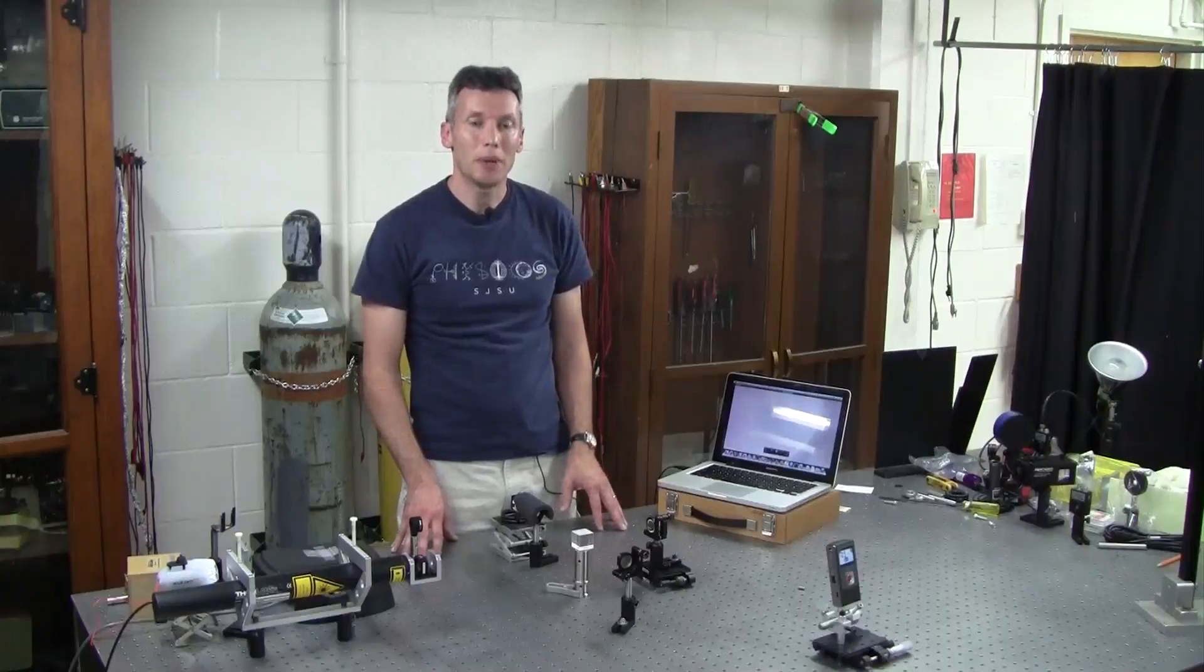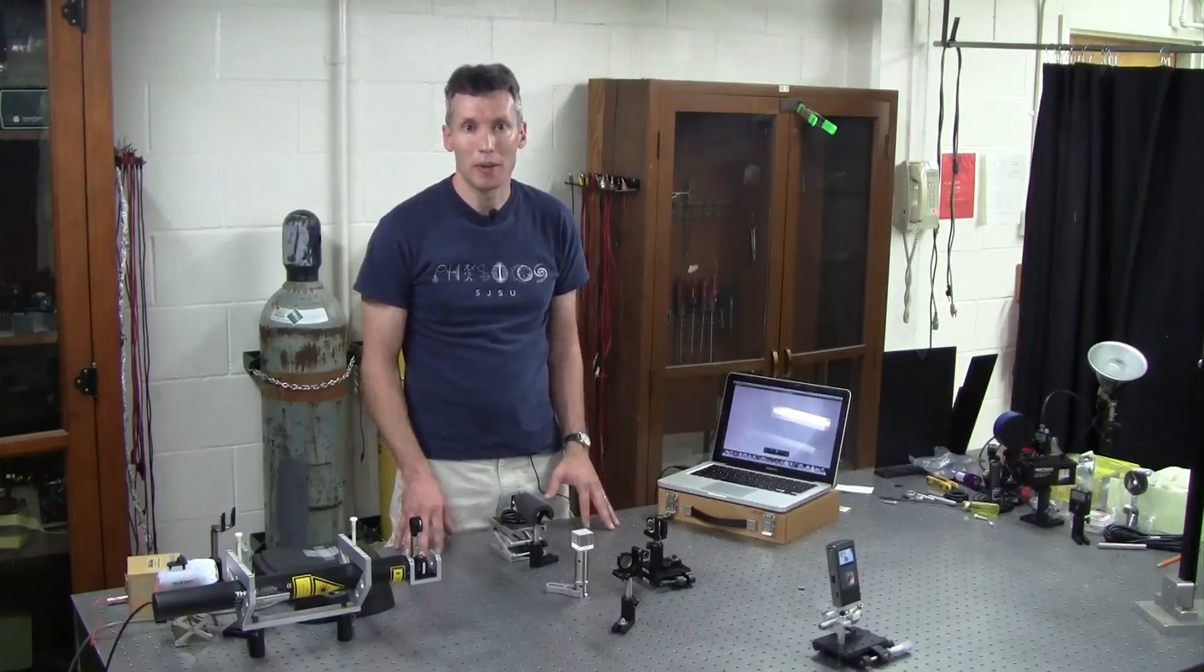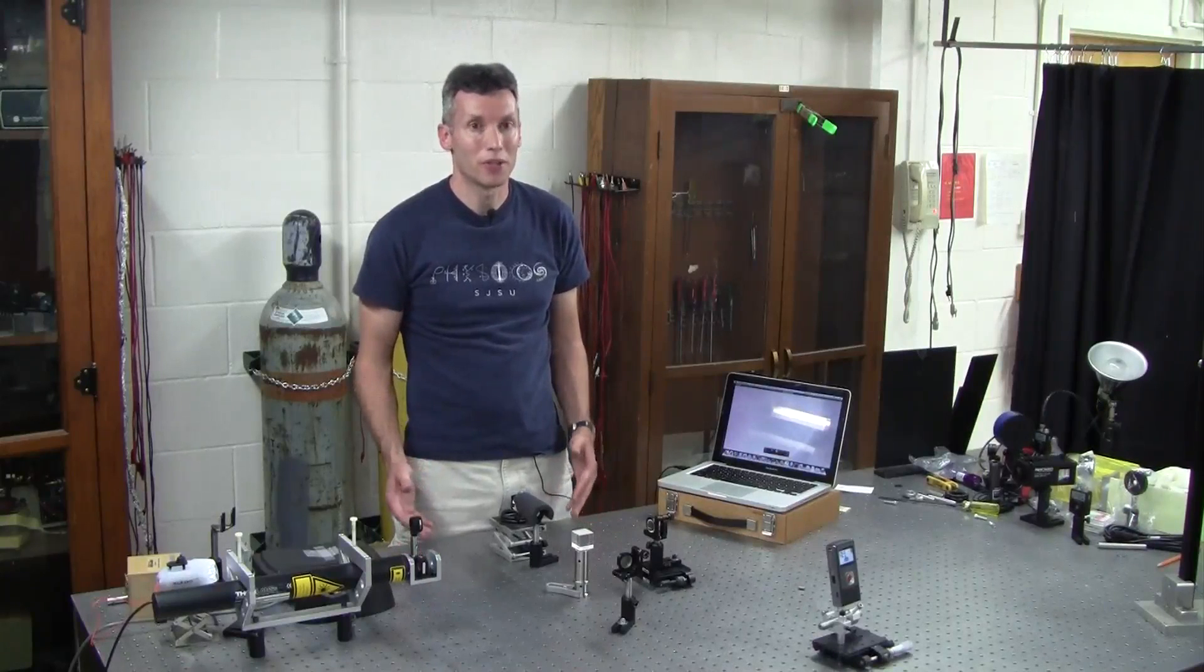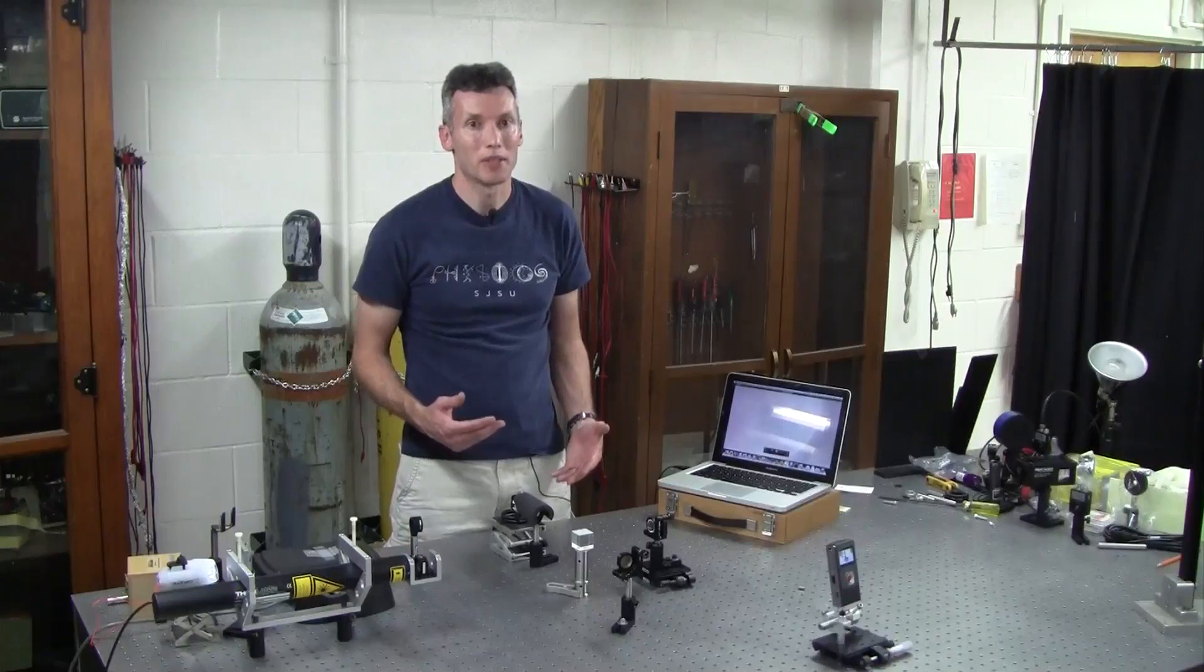The reason being is that we typically make some coarse adjustments to the alignment of the mirrors in an interferometer, acquire interference fringes, and then use those fringes to make the fine adjustments to the mirrors.